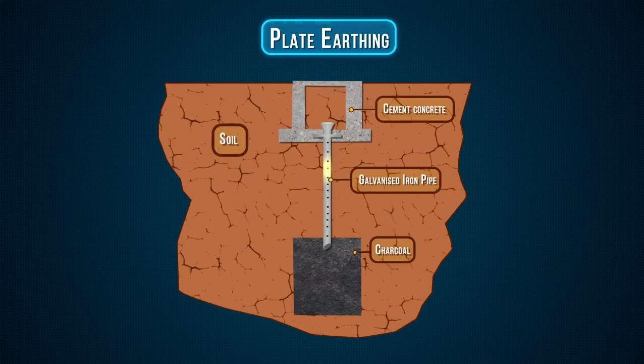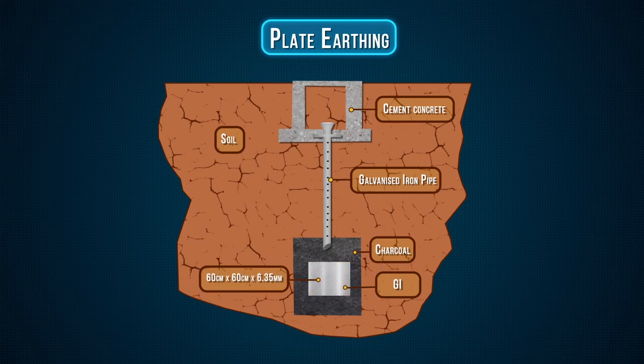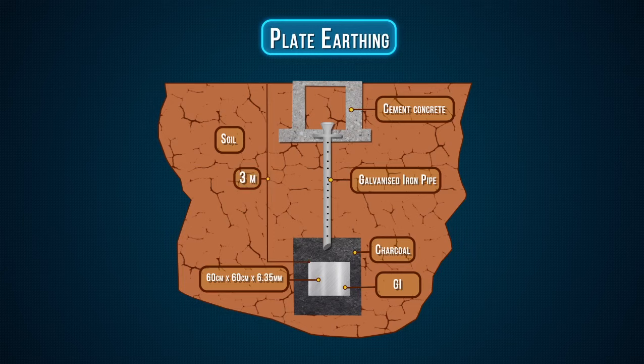Plate earthing. Look at this design for details. In plate earthing system, a plate made up of either copper with dimension 60 cm × 60 cm × 3.18 mm, or galvanized iron of dimensions 60 cm × 60 cm × 6.35 mm, is buried vertically in the earth, which should not be less than 3 m from the ground level.